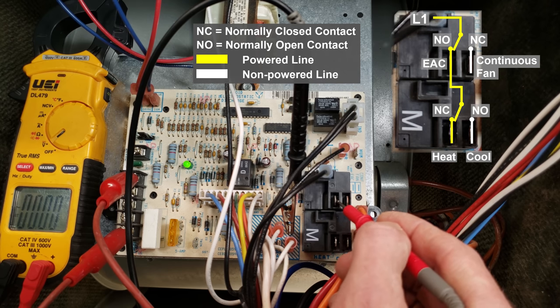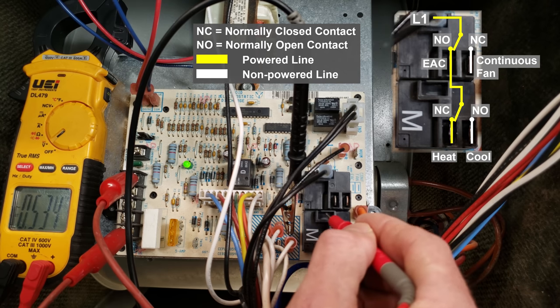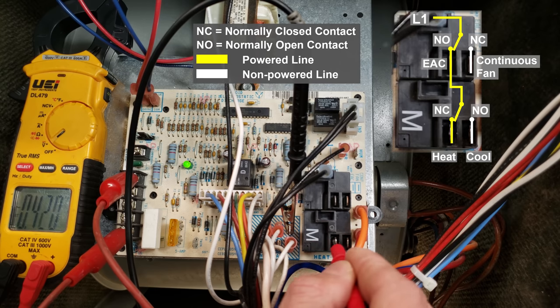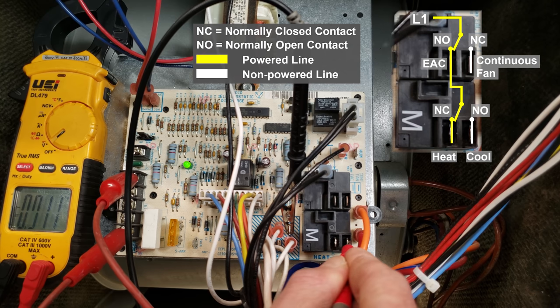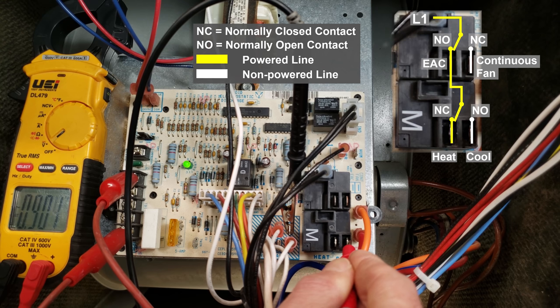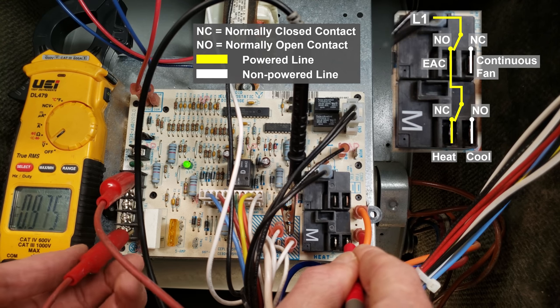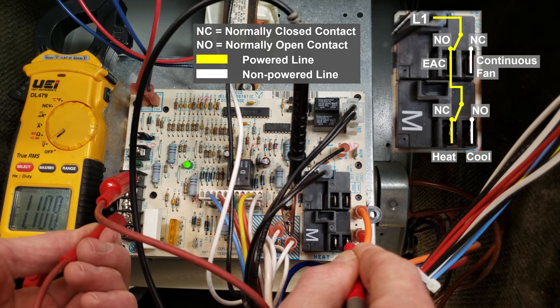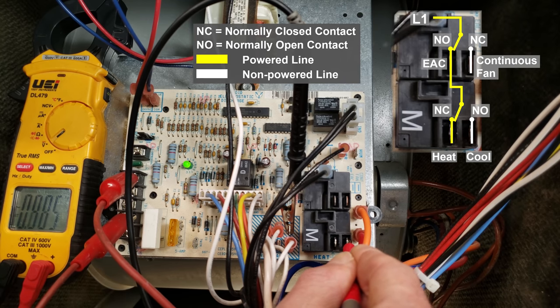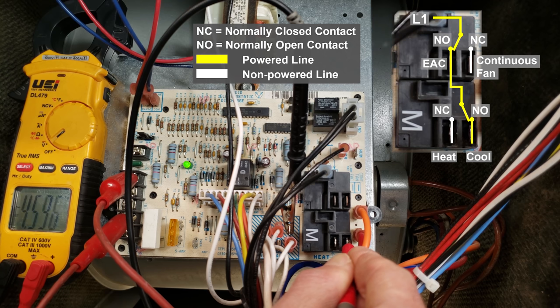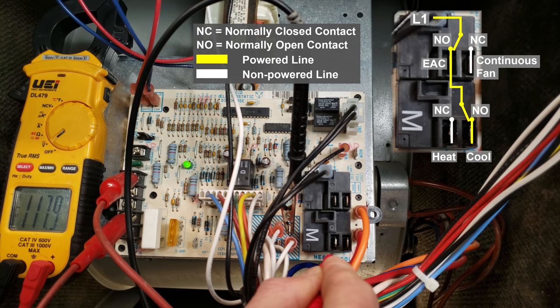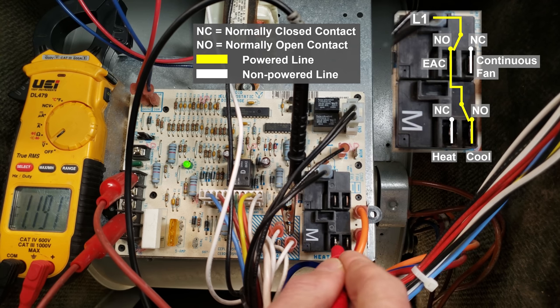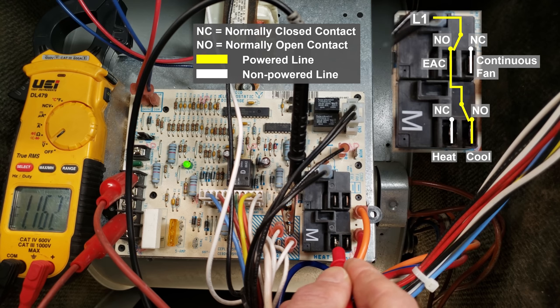Now we come down to here. This relay is normally closed to your heat and so you're going to see 118 volts. We have no power over to our cooling tap. What I'm going to do now is switch these terminals from R to G and now I'm going to touch from R to Y instead. Now you may have heard that click and you see now we're measuring 118 volts on the cooling tap and we read nothing on our heat tap.